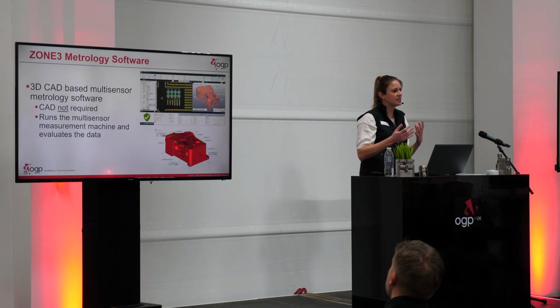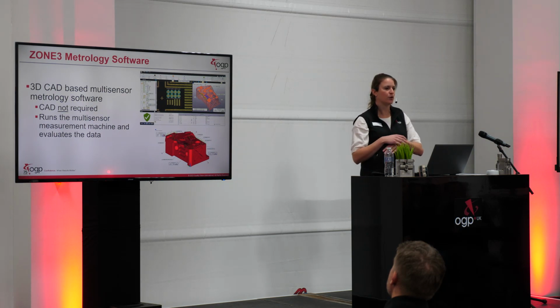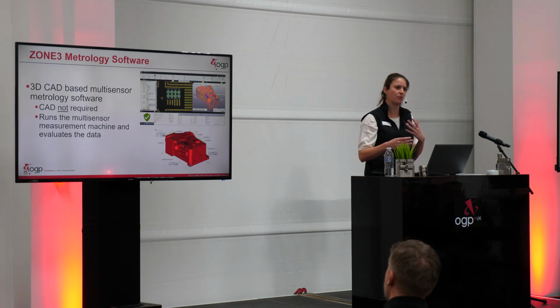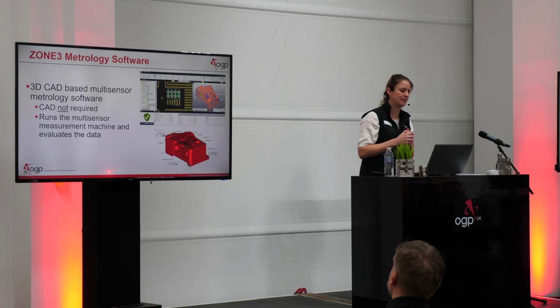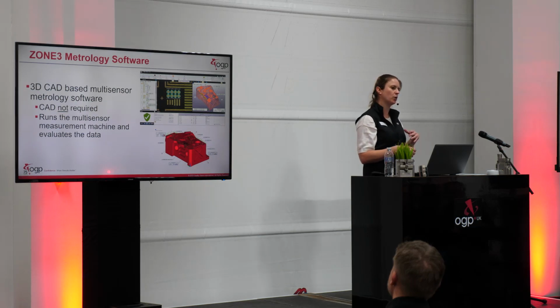So it's CAD-based, meaning a lot of the tools and a lot of the unique features of ZONE3 require a CAD model to use, but you don't need a CAD model to use ZONE3. You can program with a 2D CAD model, you can program with no CAD model. The software is for any application, but its unique features are related to CAD. And it runs our machines and evaluates the data. So you use ZONE3 to acquire the points and also do the analysis to get your measurement results.